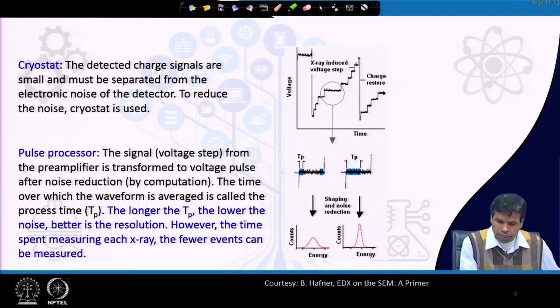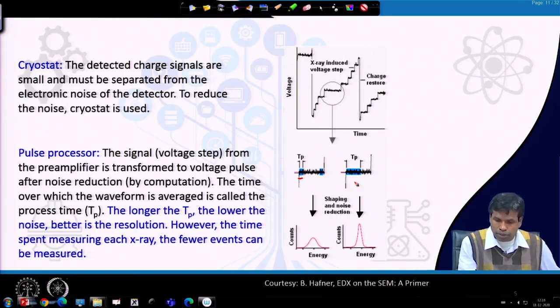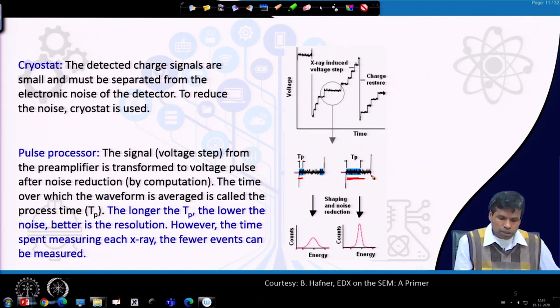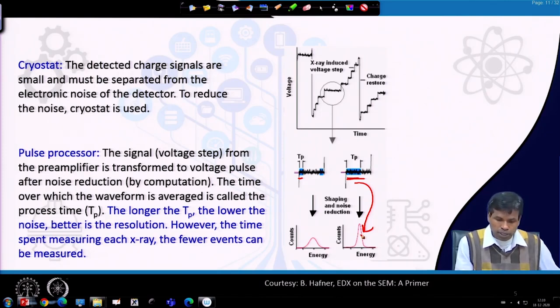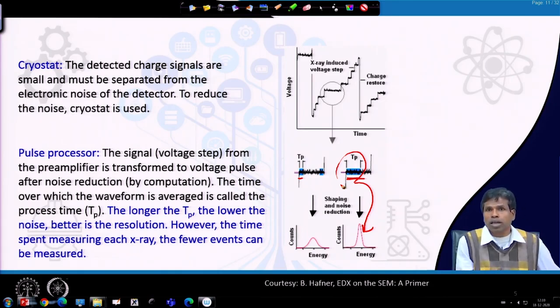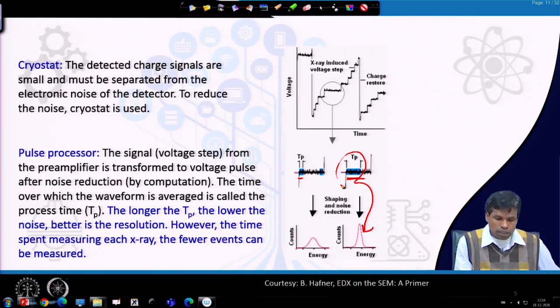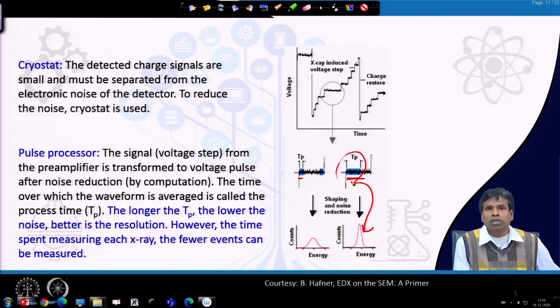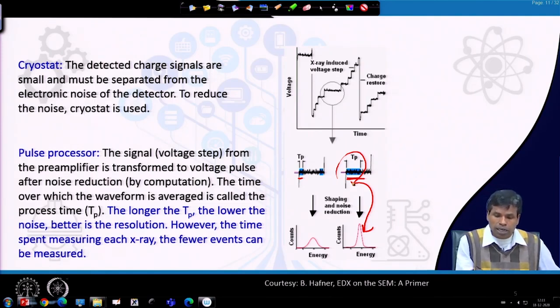The process time can be small or large. By increasing the process time we can improve the resolution — you can see a waveform with a smaller full width at half maximum, so resolution will be higher. But if we increase the process time, then fewer events will be measured, because during the time we are processing the signal we will not collect additional signals received by the detector.